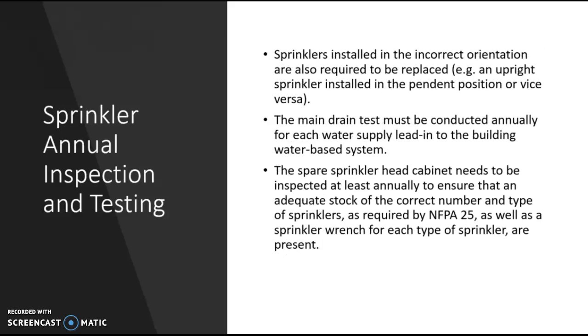Which leads me to the next annual inspection and testing, which is sprinklers installed in the incorrect orientation are also required to be replaced. For example, an upright sprinkler installed in the pendent position, or if the pendent was installed in an upright position. The main drain test must be conducted annually for each water supply lead into the building water-based system. So this is somewhat new for NFPA 25, and this is a requirement as well.